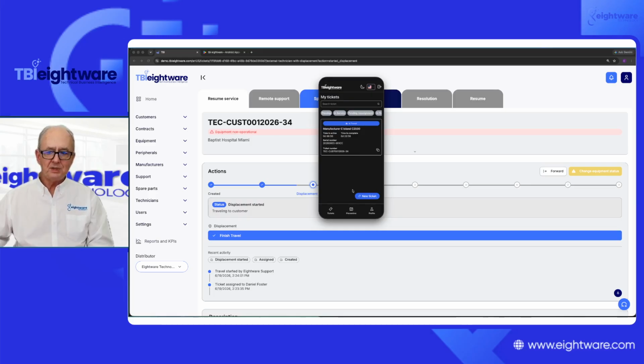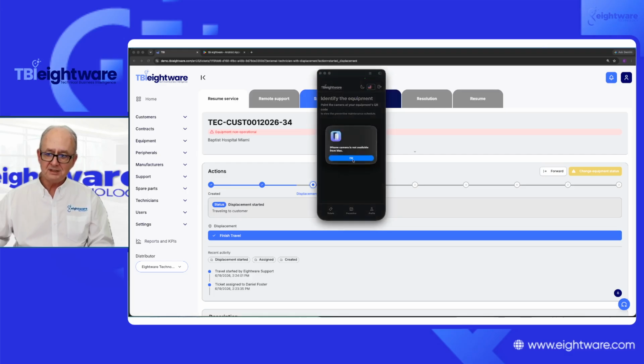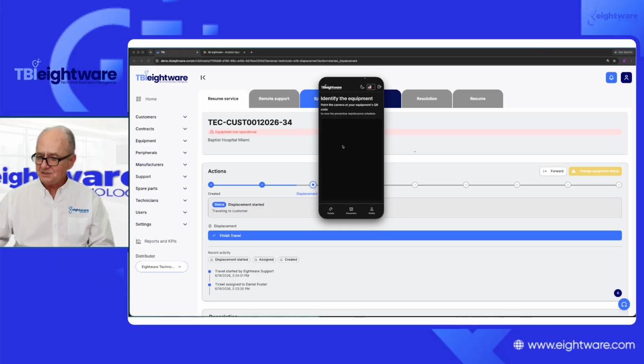If this instrument has a preventive maintenance booked, you just scan the QR code here and you will see the preventive maintenance schedule. Let me see here if they have. I believe no, they don't have. This customer doesn't have preventive maintenance programmed yet. It's just an example, but it works the same way.